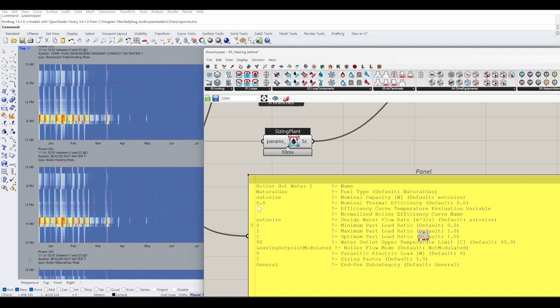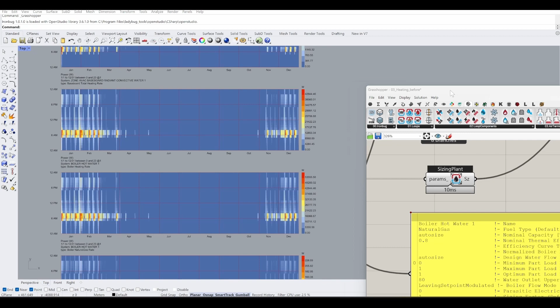And what's next? The pump electricity rate and the pump mass flow rate, so how much water is going through this pump. If you check the pattern here, whenever the value is not 0, that means the pump is running, and that's hot water going through the boiler as well. You can check the schedule pattern. They are all matching together. That makes sense.